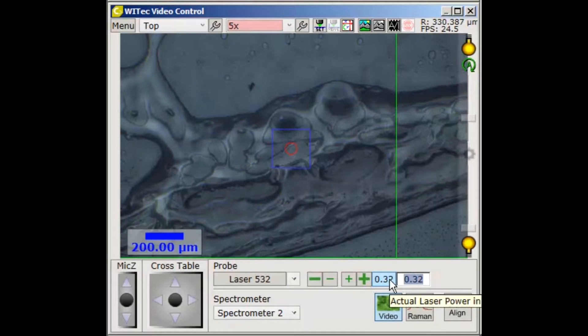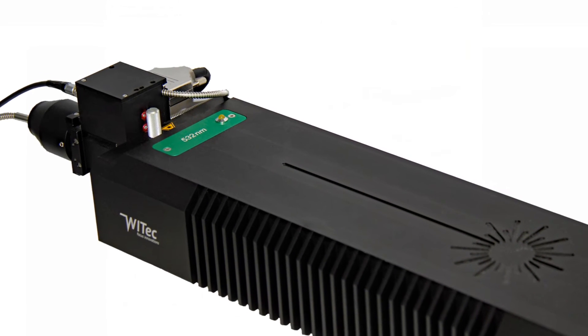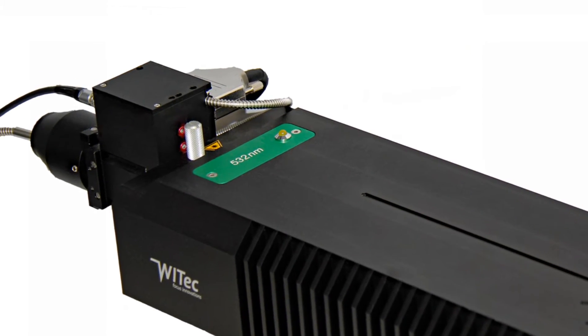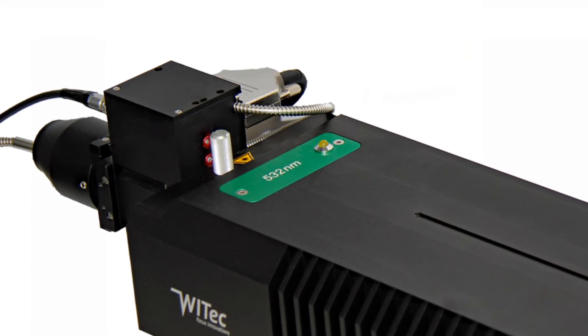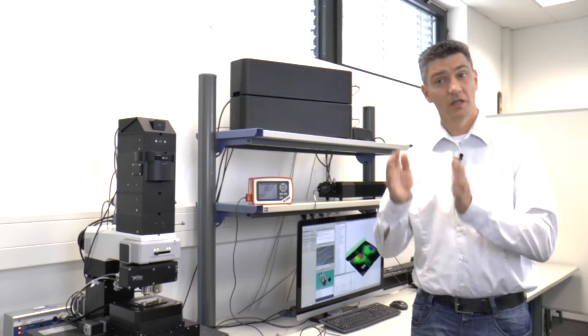The big advantage is in addition that with this true power module you set the power without the shutter being open that means you don't expose your sample to laser power while you find the right setting. So with the true power you can set an arbitrary power within the fiber in milliwatts. It's not relative values such as when you use neutral density filter so you get 50 percent 10 percent 5 percent or something like this it's absolute value in milliwatts.